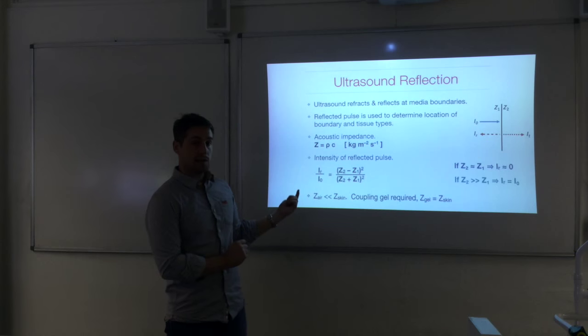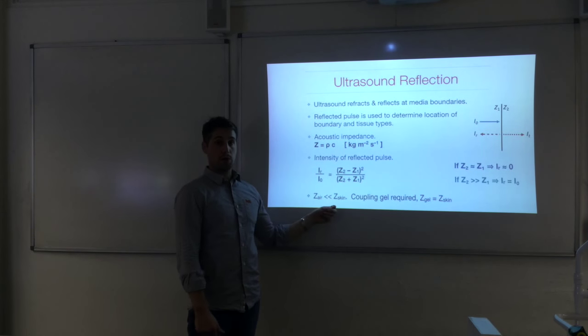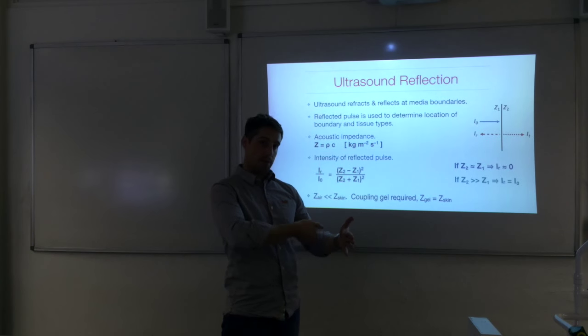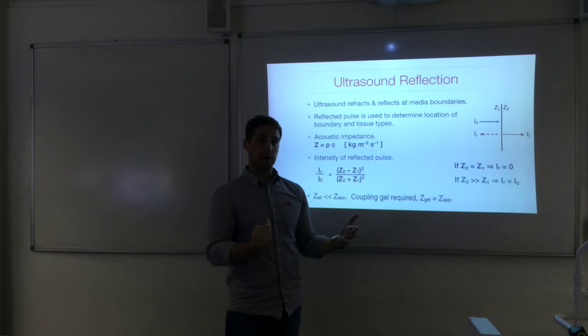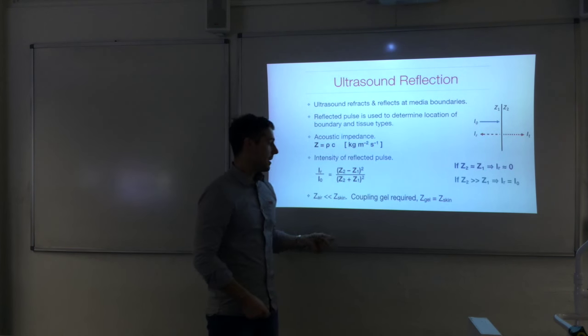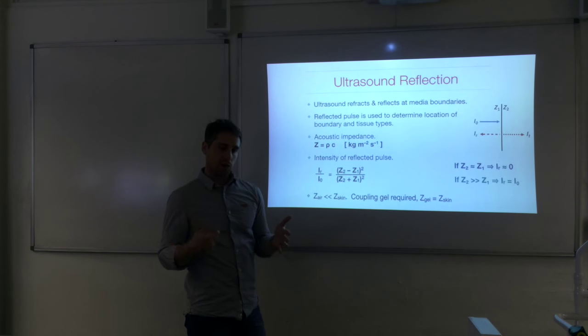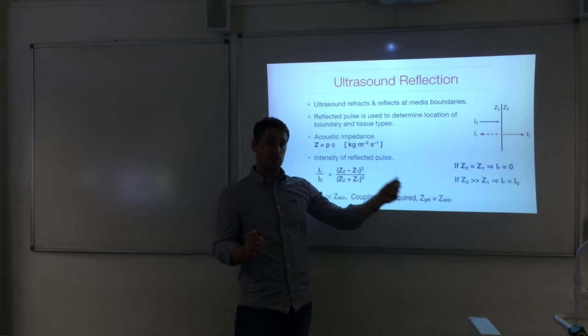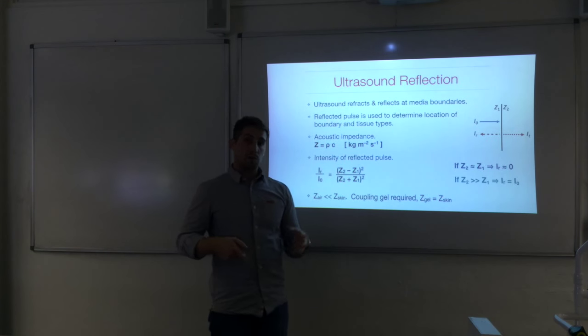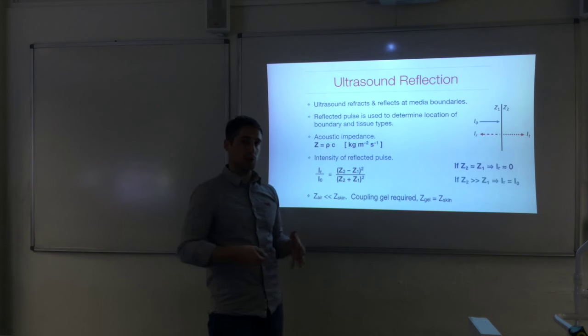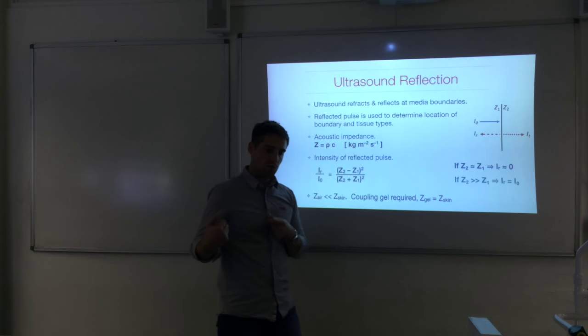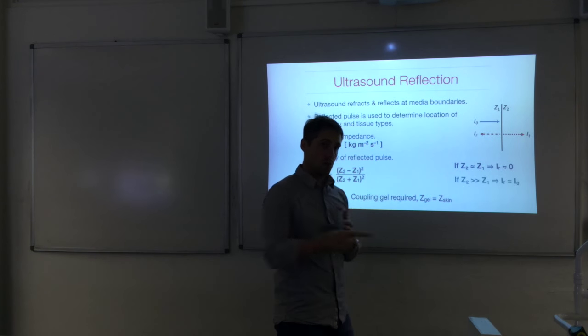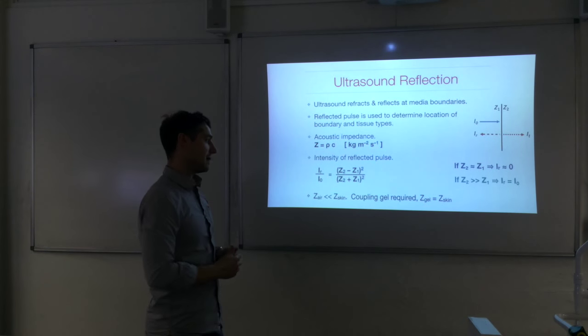Air has a very low acoustic impedance, much lower than skin. So if the ultrasound transducer is held in air near skin, most of the ultrasound will just bounce off and not enter the body. Therefore, when using an ultrasound transducer effectively, you need a coupling gel. The coupling gel has an acoustic impedance roughly equal to that of skin, so the ultrasound travels from the gel into the skin and into the body without significant reflection at the surface.